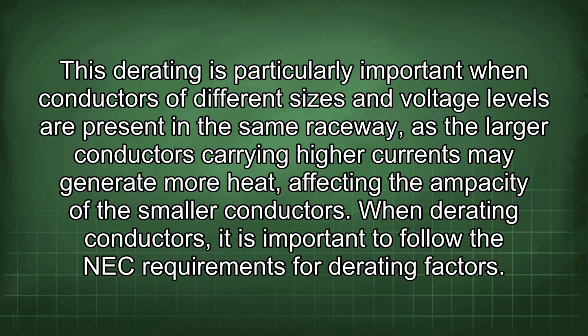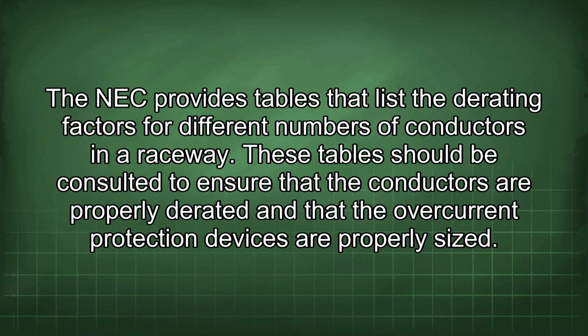This derating is particularly important when conductors of different sizes and voltage levels are present in the same raceway, as the larger conductors carrying higher currents may generate more heat, affecting the ampacity of the smaller conductors. When derating conductors, it is important to follow the NEC requirements for derating factors. The NEC provides tables that list the derating factors for different numbers of conductors in a raceway.